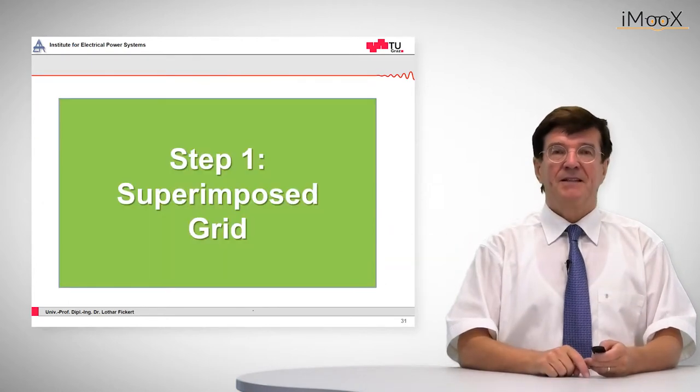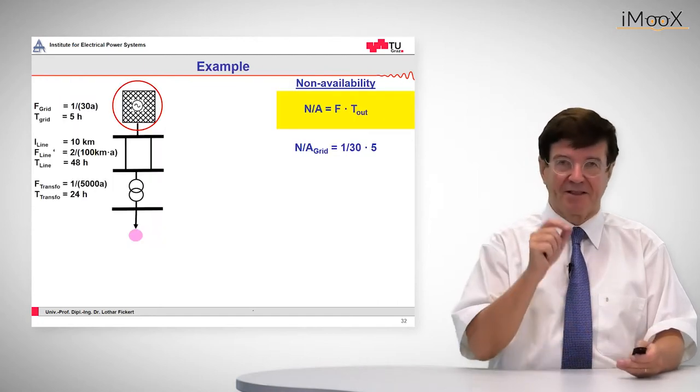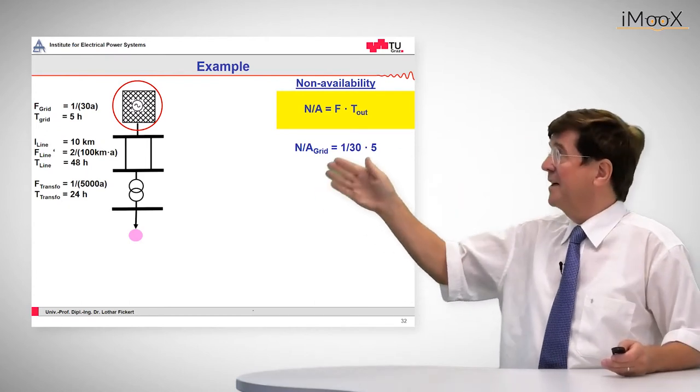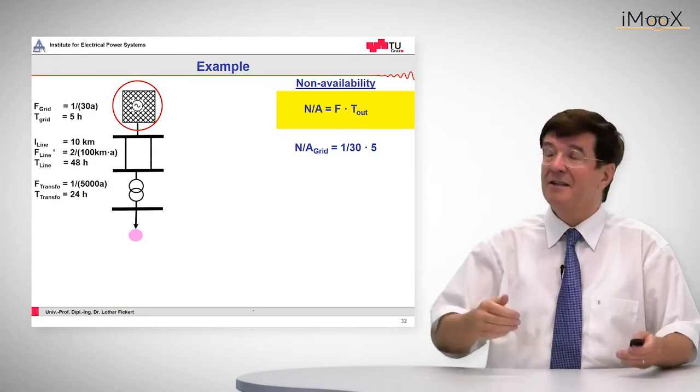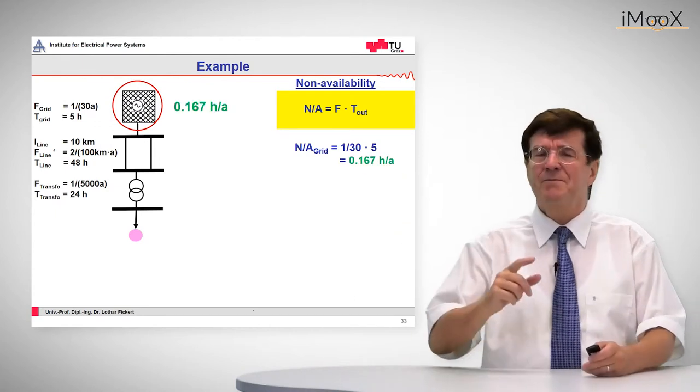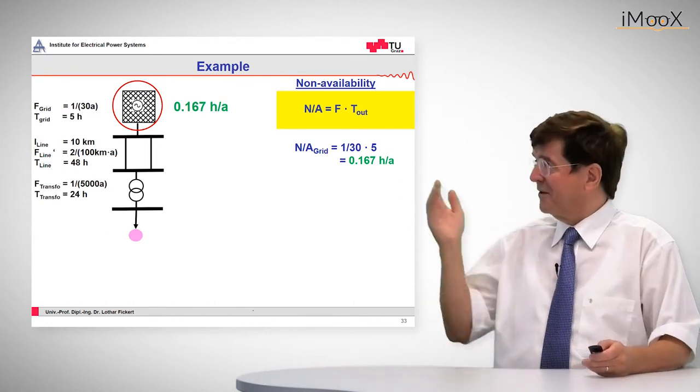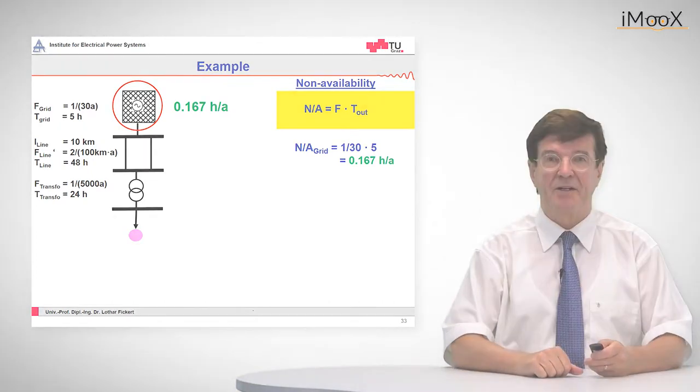The superimposed grid is given by the basic formula: non-availability is the product of frequency of occurrence of faults and the average outage time. This is 1 divided by 30 times 5, and the unit is hours divided by year. The non-availability is 0.167 hours per year.